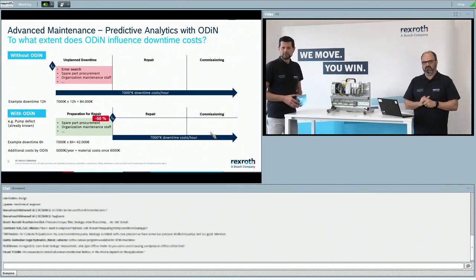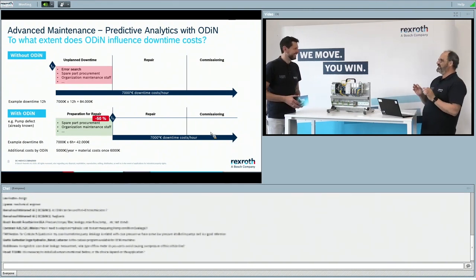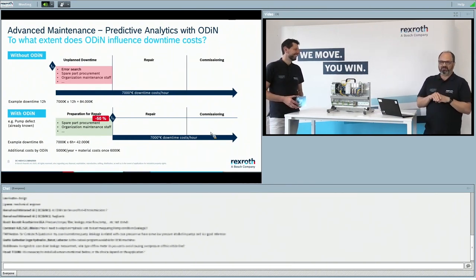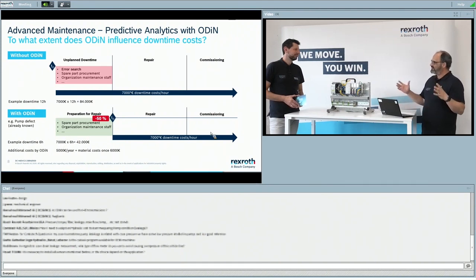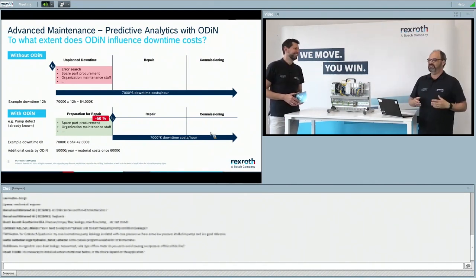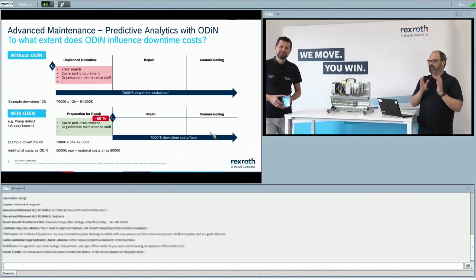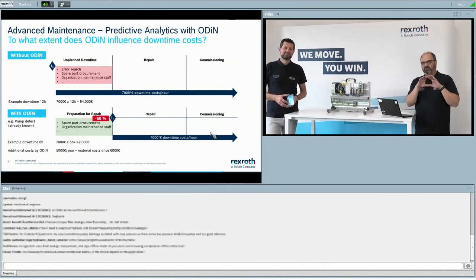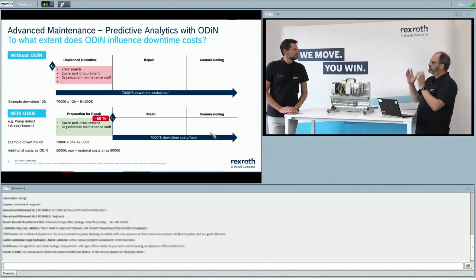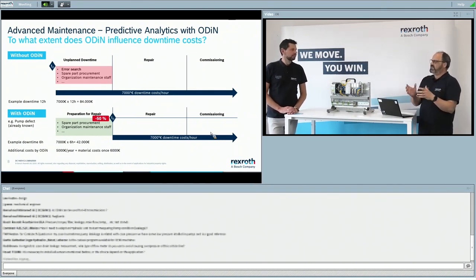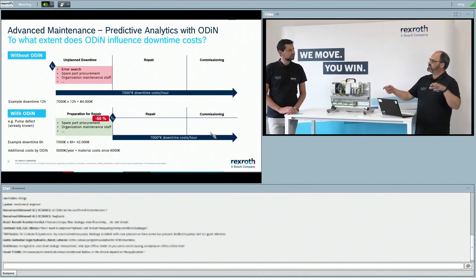Another question: is it necessary to install all sensors mentioned, or does the choice depend on the application? This is a really good question. We don't want to come with a box full of sensors and put everything on the machine. We focus on the pain points and problems directly. If the customer says their problem is with the cylinder rather than the pump, we focus on the cylinder — though sometimes we also monitor the pump because the root cause of cylinder issues actually comes from the HPU.